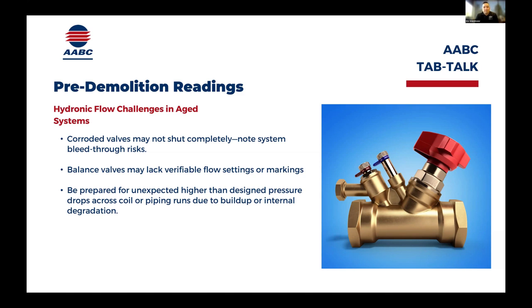If we're taking pressure drops across coils, across components, chiller barrels, there may be corrosion happening that's going to manipulate how much pressure drop we're seeing at a particular flow. So we can't always reference back to that design data. We do have to look at it from multiple standpoints.